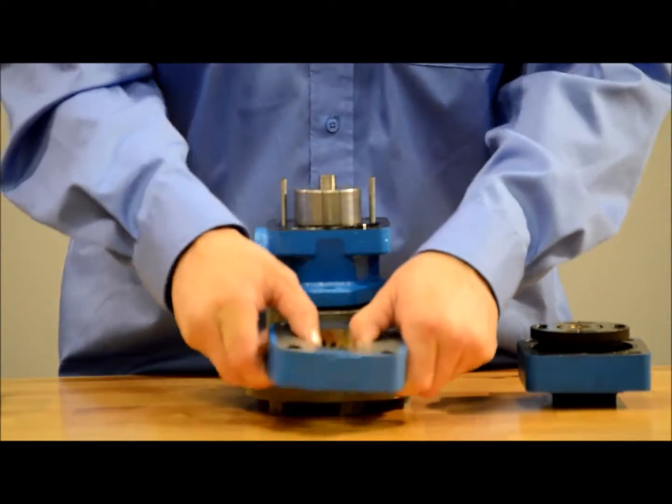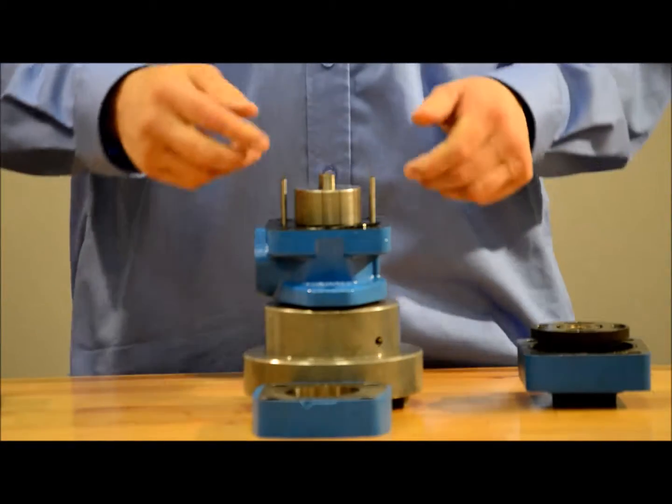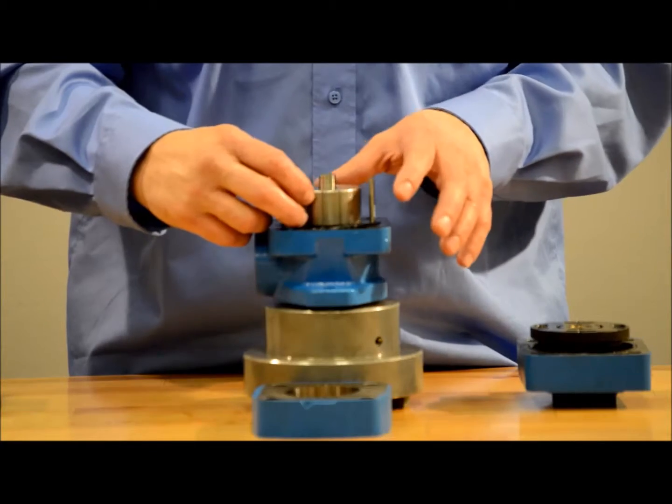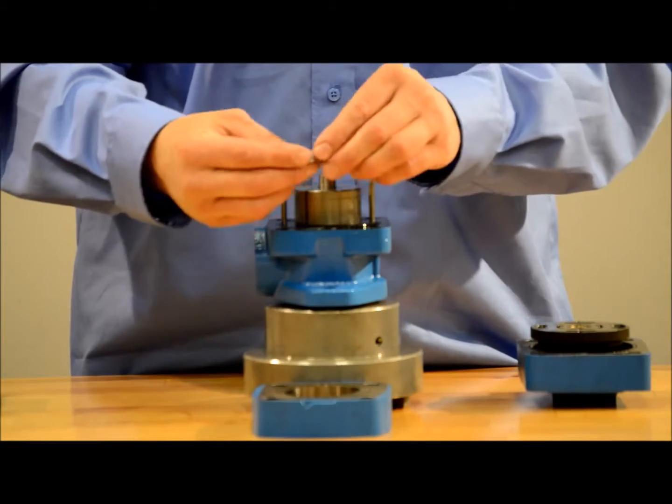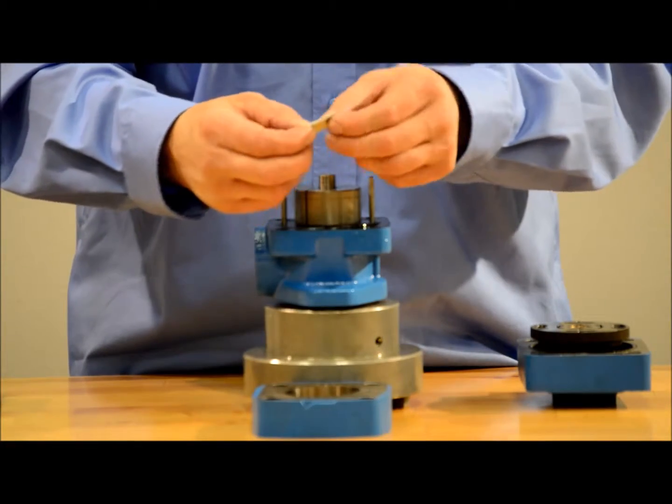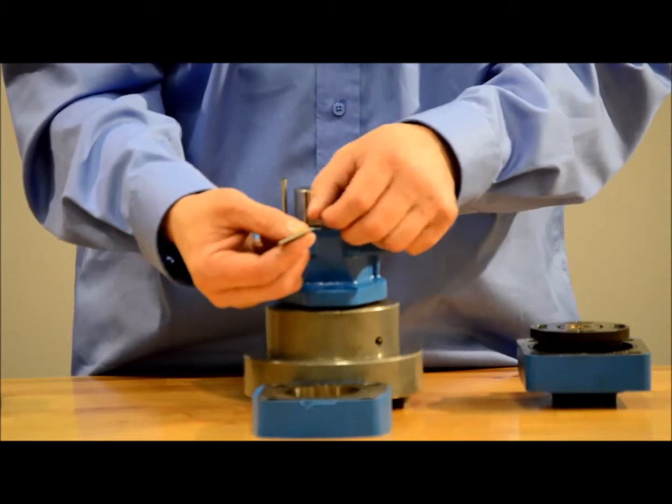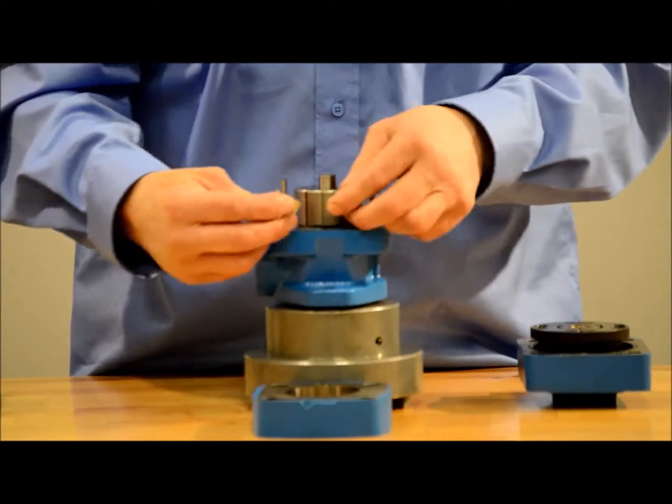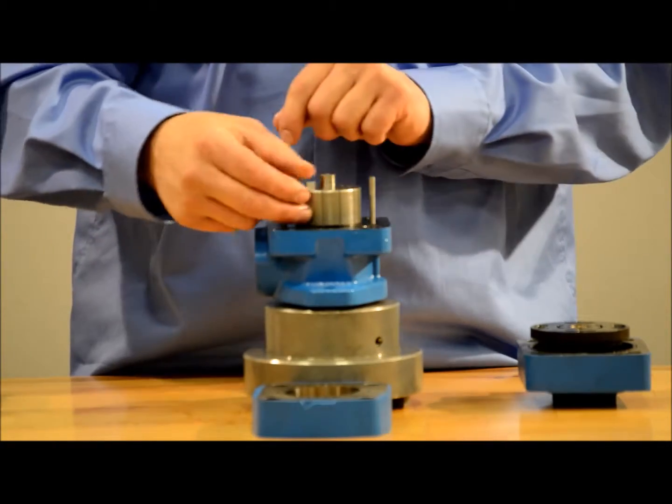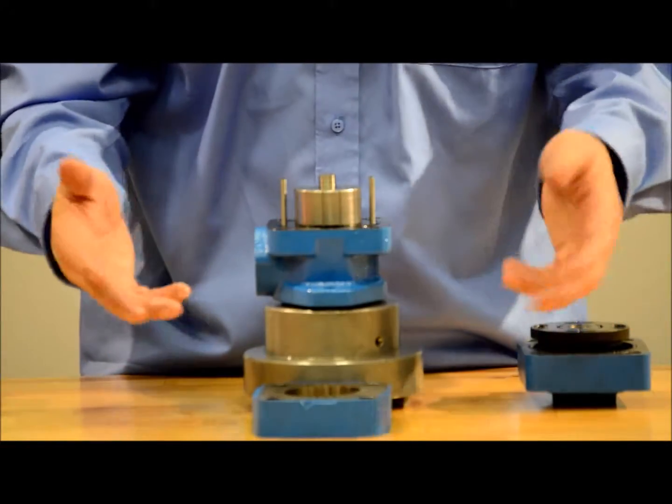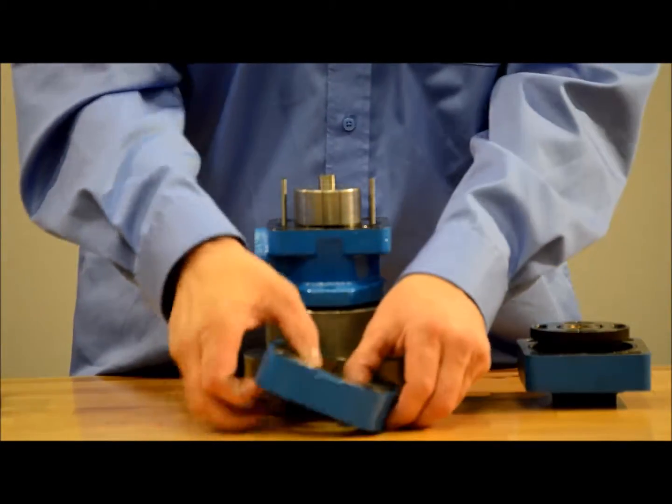So once we have the cam ring off, if you have some vanes that fall out or drop out of the rotor while you have that out, they can easily be reinstalled because they are rounded on one side and flat on the other. The flat edge goes towards the inside of the pump or towards the shaft, and the rounded edge is going to ride along this cam ring here. So if they fall out, really don't worry, no panic.